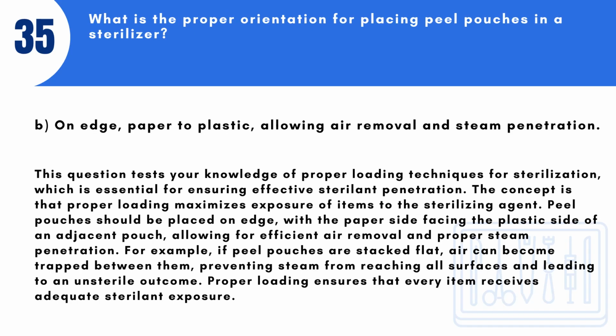Answer: B. On edge, paper to plastic, allowing air removal and steam penetration. This question tests your knowledge of proper loading techniques for sterilization, which is essential for ensuring effective sterilant penetration. The concept is that proper loading maximizes exposure of items to the sterilizing agent. Peel pouches should be placed on edge, with the paper side facing the plastic side of an adjacent pouch, allowing for efficient air removal and proper steam penetration.